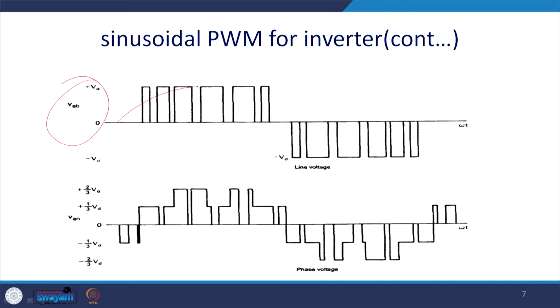Ultimately this will be equivalent to the sine wave, though the magnitude has to be less. The volt-area of the sine wave and the actual PWM pulses has to match, so there will be an instantaneous voltage difference between the sine wave and the actual voltage injected. That is the cause of harmonics, because there is an instantaneous error, and that gap gets filled by the harmonics.